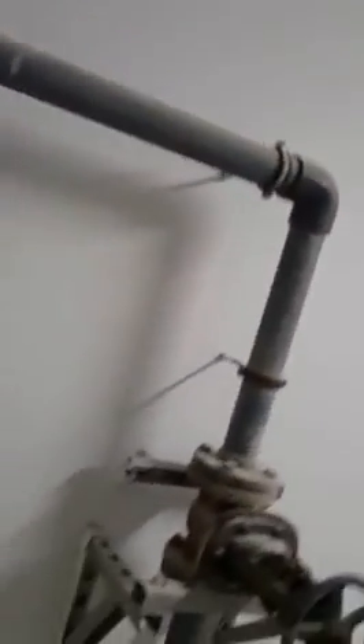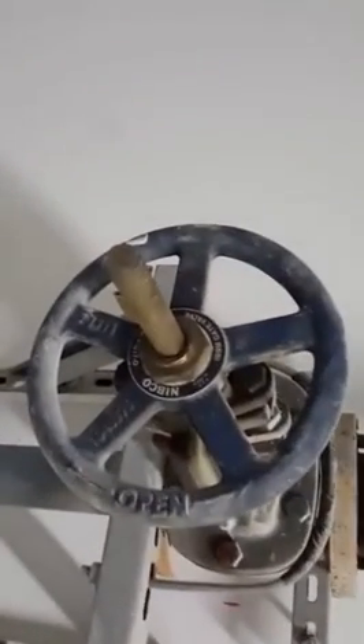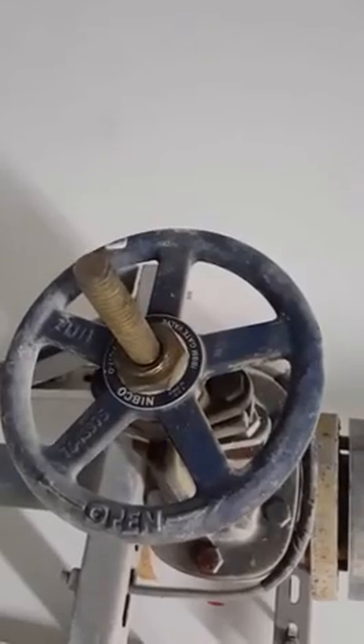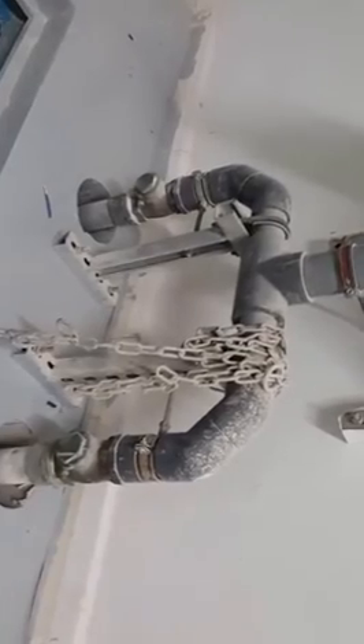This pipe is going to the manhole because this is what we call the force main line. This is the gate valve — you can see it here — from the NIBCO company. And this is the check valve. The check valve function is that water will not return back; when the pump stops, water on the pipe side will not come back down.